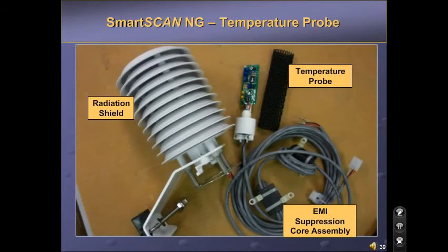This photograph shows the temperature probe components. There are three basic parts: the radiation shield, the EMI suppressor assembly, and the temperature probe circuit board. Over the years, there have been a number of changes to the temperature probe. The EMI suppressor assembly, along with the metal ring on the bottom of the shield, reduce the possibility of RF interference getting into the system. The circuit boards are also now potted in a polyurethane compound to make them better weather resistant.